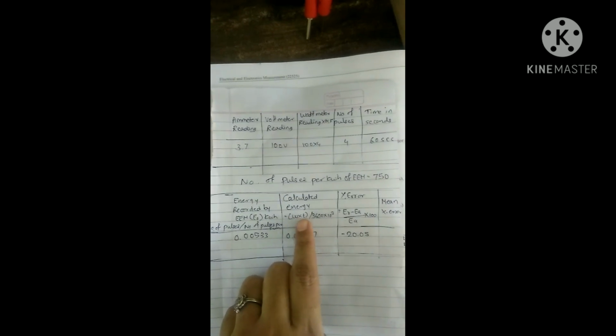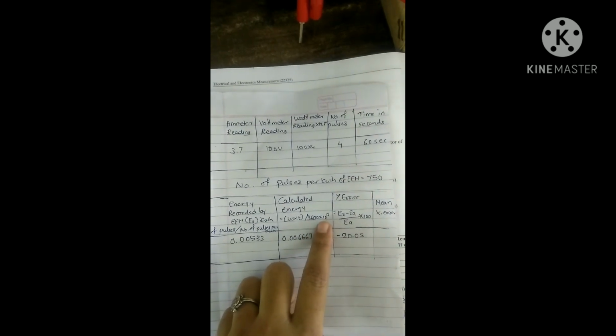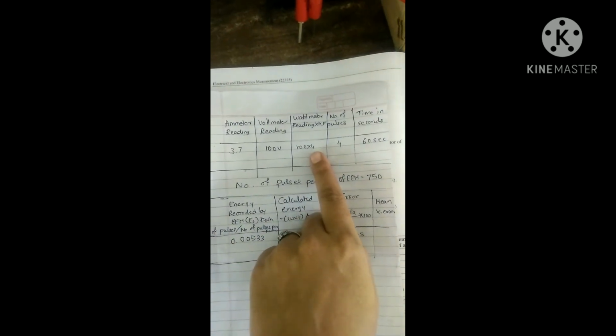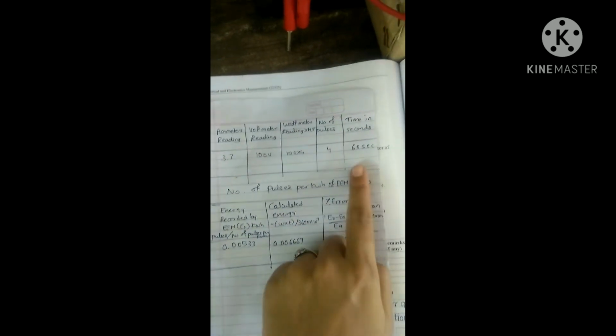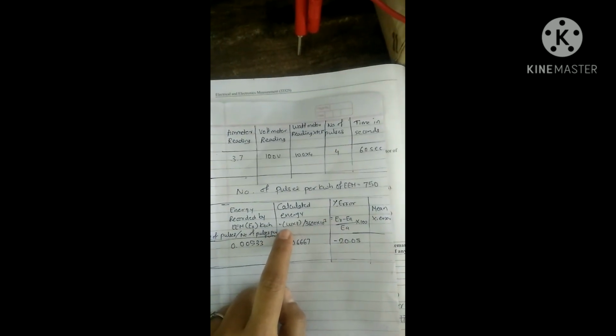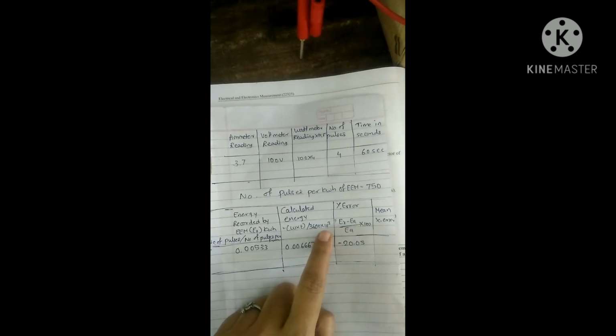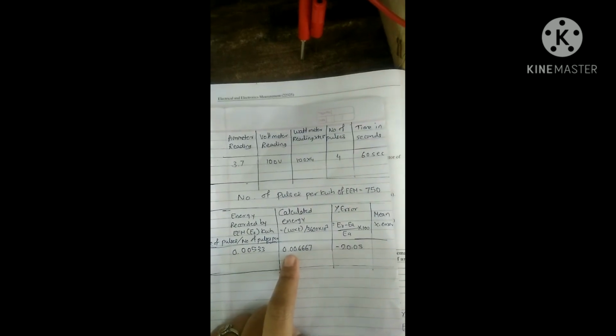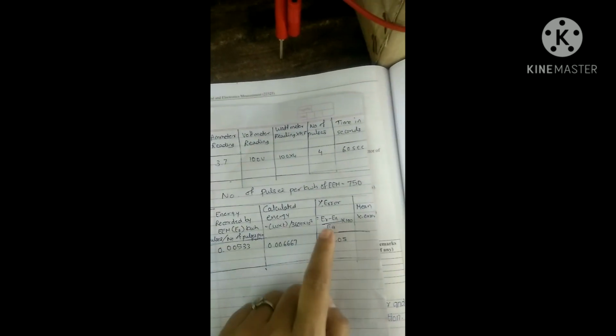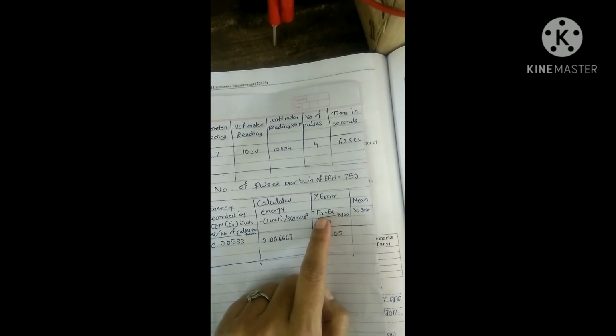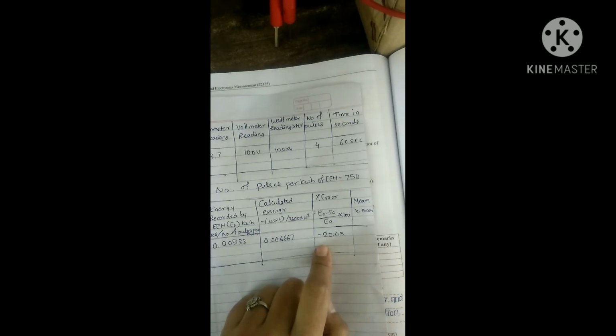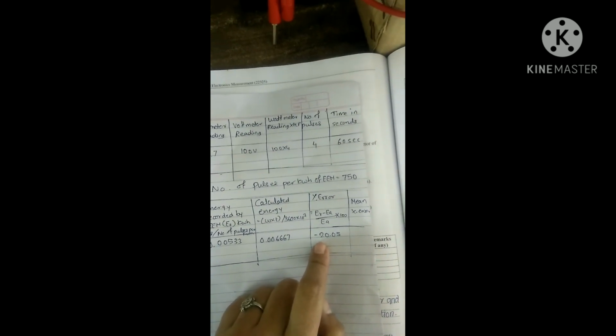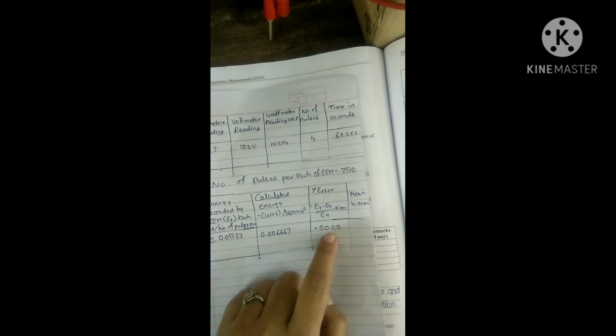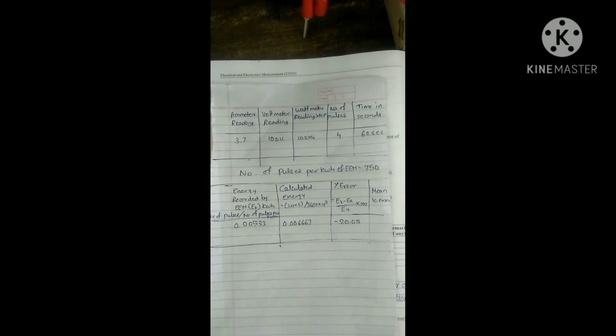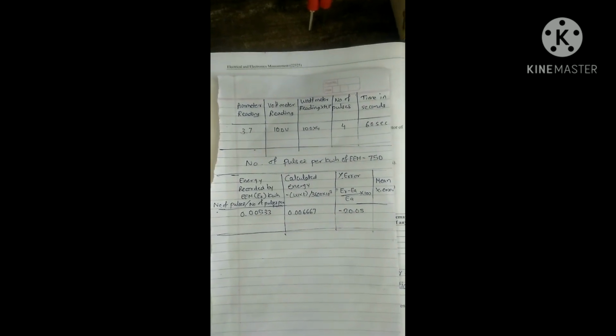Next you have to calculate calculated energy. Formula for this is W into T upon 3600 into 10 raised to 3. So W is wattmeter reading. So 400 into T, that is 60. So 400 into 60 divided by 3600 into 10 raised to 3, which becomes 0.006667. Next you have to calculate percentage error. Formula for this is ER minus EA upon EA into 100. So by calculating this, you can have the value which is minus 0.05.